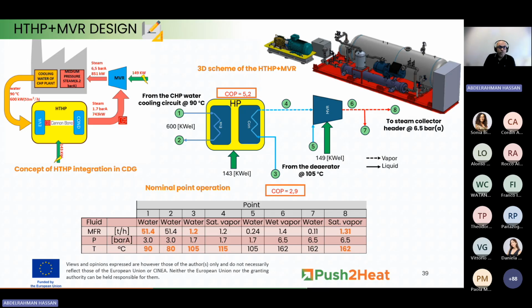Here you can see the details of the nominal operating point. On the source side, the inlet temperature will be 90 degrees from the cooling circuit. We will extract 600 kilowatts. On the sink side, we will use the water from the deaerator at 105 to increase its temperature, preheating it to 115, and we will produce saturated steam at 115, at point 4, which corresponds to 1.7 bar A.